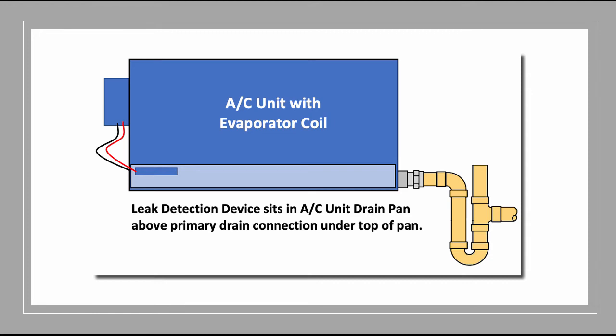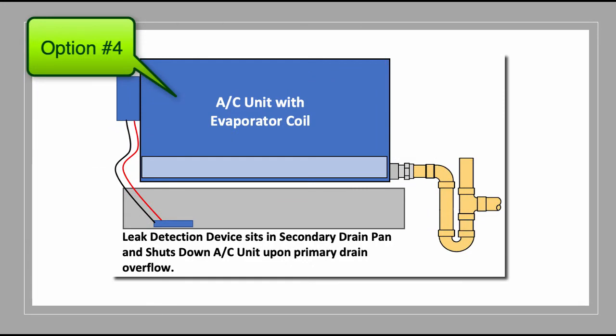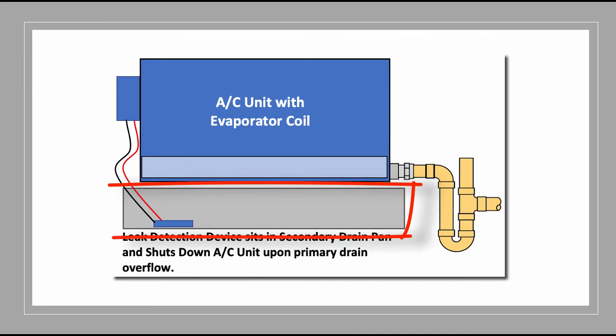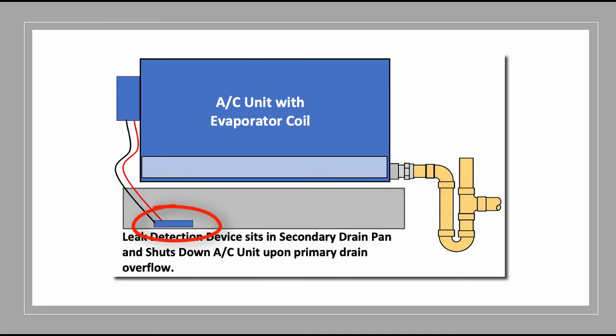Option four is similar. You'll put a secondary drain pan with a leak detection device on the bottom of the pan. If the primary pan overflows and starts to leak into the secondary pan, the secondary pan will catch it and the leak detection device will shut off the air conditioner from running any further. On that secondary drain pan, there is no secondary drain piping if you're using the leak detection device as the protection method to shut down the unit.